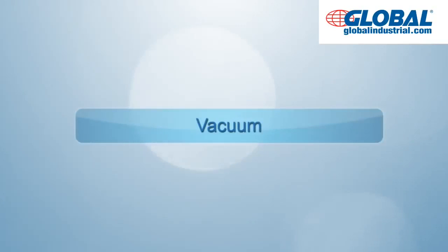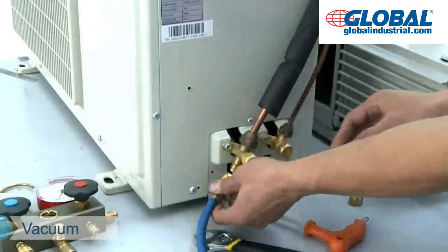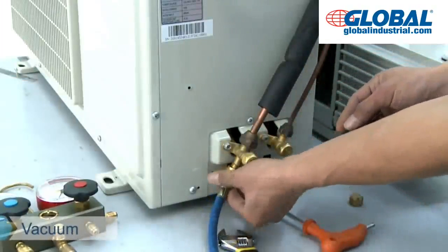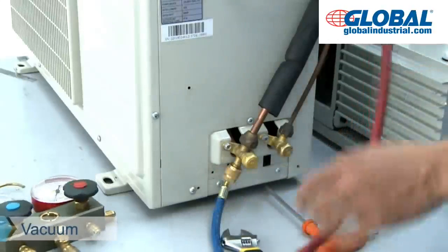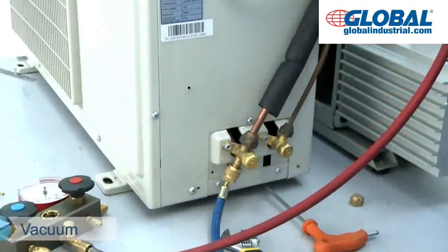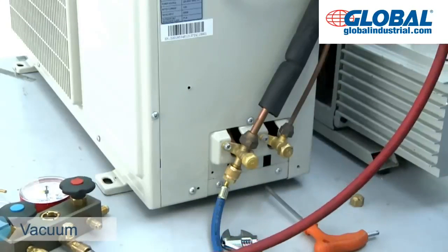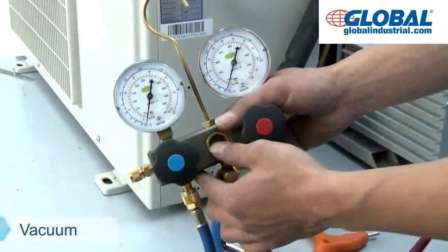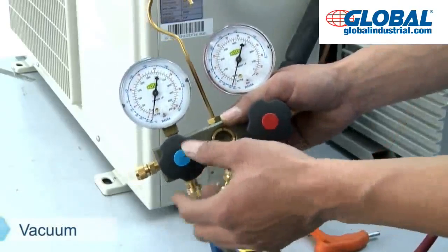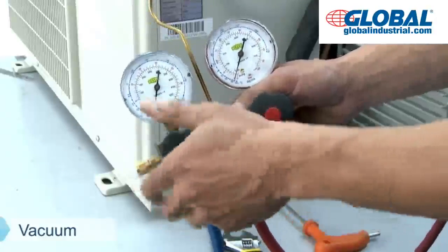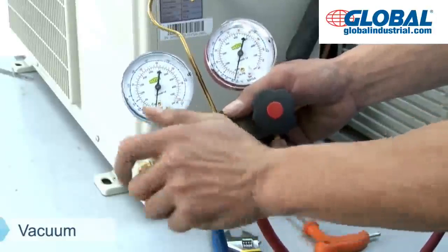Vacuum. Connection of vacuum pump. One end of the filler wire of pressure gauge should be connected to the vent of vacuum pump. The other end is connected to filler mouth of low pressure valve. Open low pressure valve of pressure gauge. Keep high pressure valve closed normally.